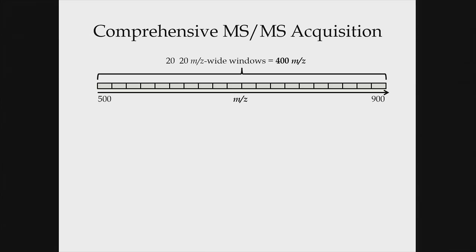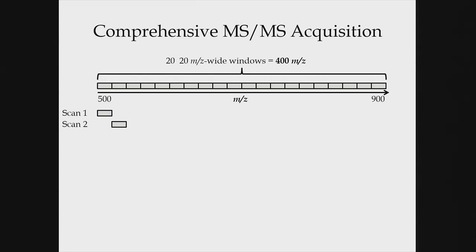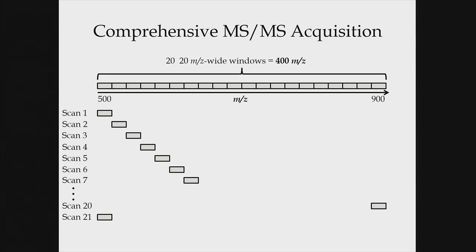When I talk about comprehensive MS/MS acquisition, we're acquiring a cycle of MS/MS scans. The reason this is called data independent is because we're not basing our MS/MS scans on decisions from MS1. In DDA, we look in MS1 and say, 'Do I see a signal? Then I'll do an MS/MS for that precursor.' With DIA, we acquire a repeated cycle of MS/MS completely independent of any MS1 information. Our first scan is a wide isolation window MS2 — say 20 m/z wide — and the next scan is adjacent, covering 520–540 m/z. By scan 20, we've comprehensively covered the 500 to 900 m/z range.